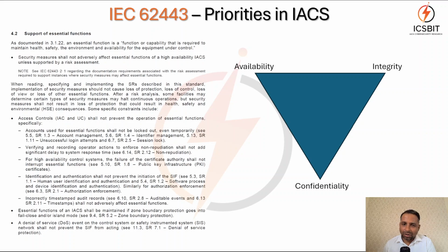Confidentiality is definitely an important concept which we have to take care of. But because of the very nature of the functionality and the requirements of the environment, many times we give a lot of laxity when it comes to confidentiality. For example, we might not have passwords on a few of the HMIs which are taking care of alarms and events. That's very important, because any operator in the control room shall operate this HMI without any restrictions and within the given time.